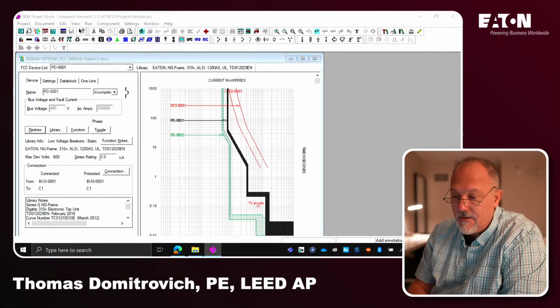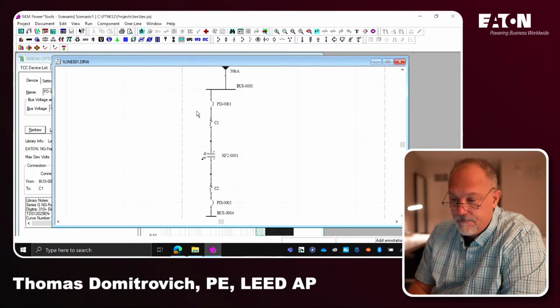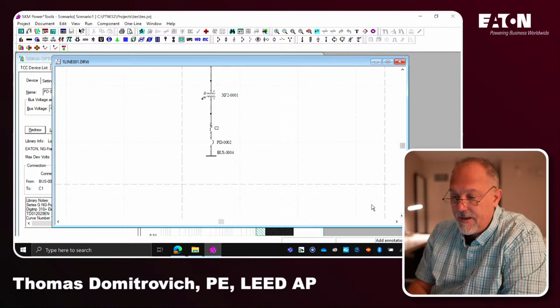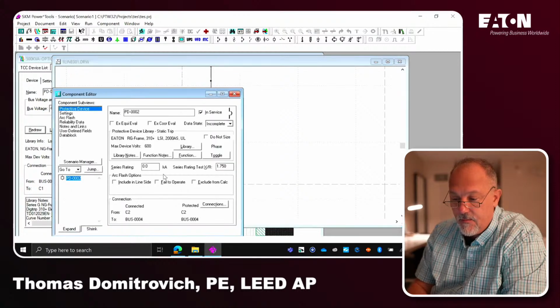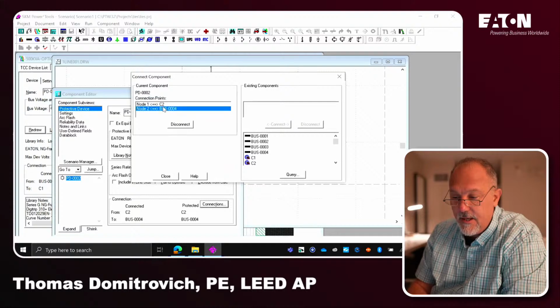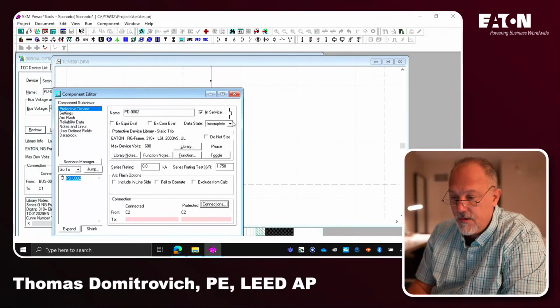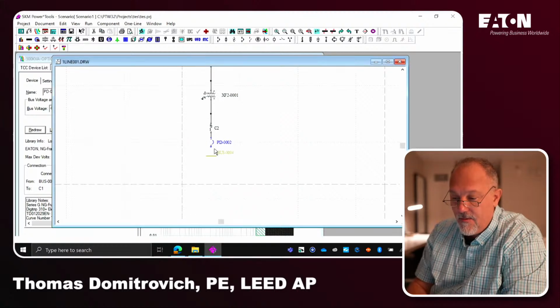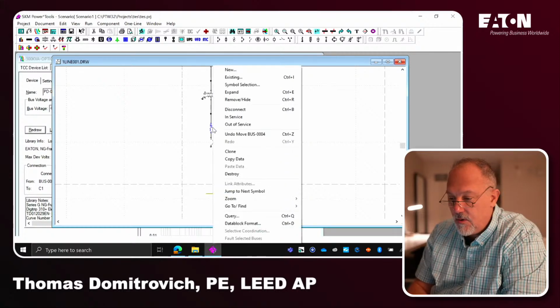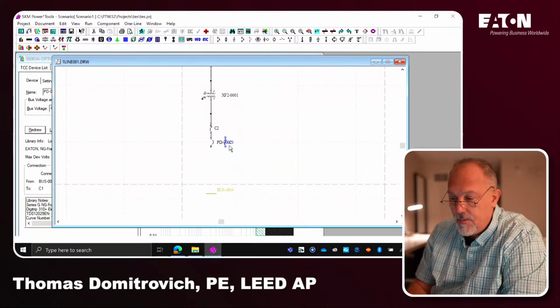All right, so now we're in scenario 1. I'm going to go back to the one-line diagram, and here is what we're going to do. We're going to come down here on the secondary. We are going to double click on this, go to the secondary connection, and disconnect. Hit close. So now we're going to roll this down and add a conductor. Actually, can I copy this? Clone. Boom, I cloned that conductor, so I have the exact same conductor, and I am going to add 10 feet of that puppy right here.